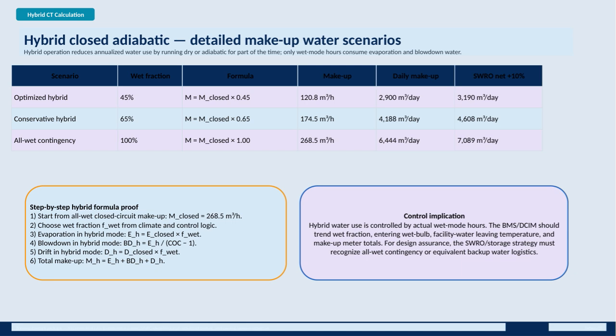This slide outlines a training concept package built around Badham's coastal data center water supply, integrating SWRO desalination, direct liquid cooling, and the cooling tower system. We see three scenarios comparing different wet fractions: optimized hybrid at 45%, conservative hybrid at 65%, and an all-wet contingency at 100%. The equations show how makeup water volume is adjusted by multiplying closed-circuit makeup by the wet fraction to find the daily water requirement.